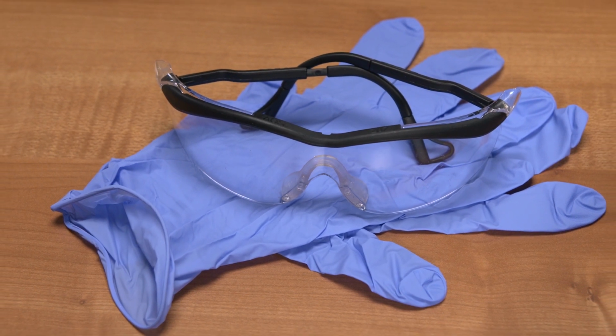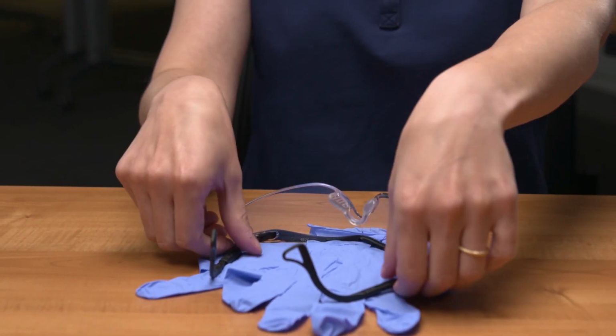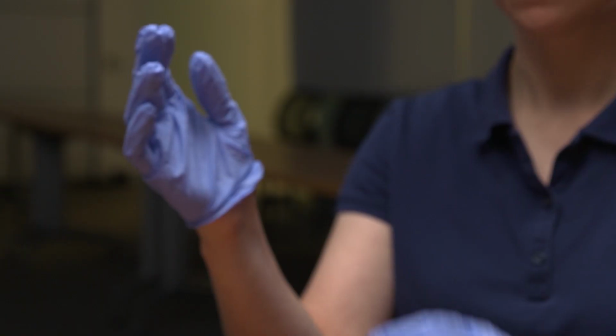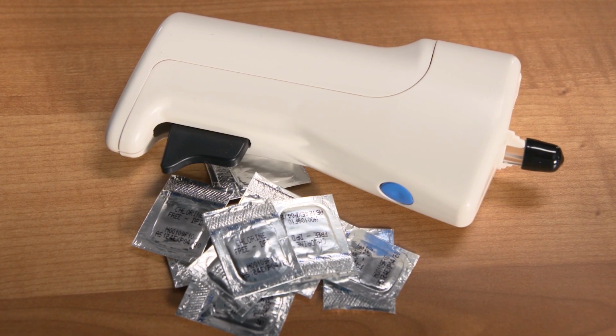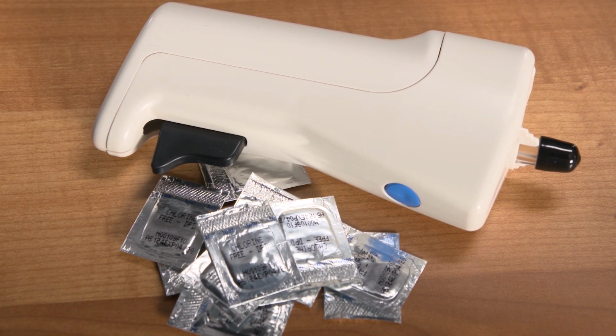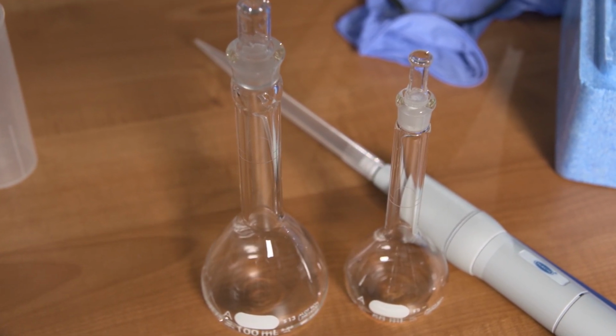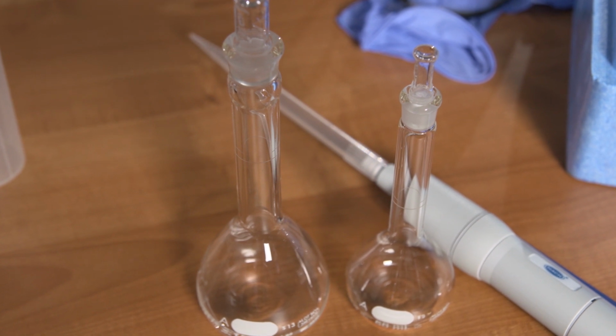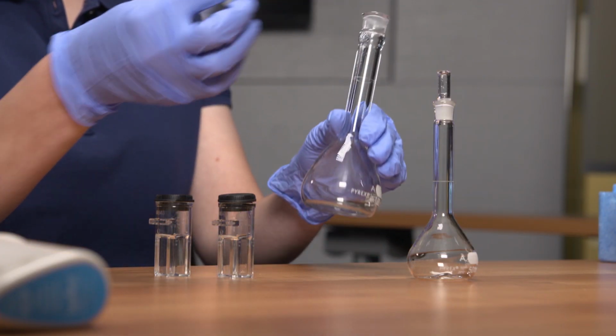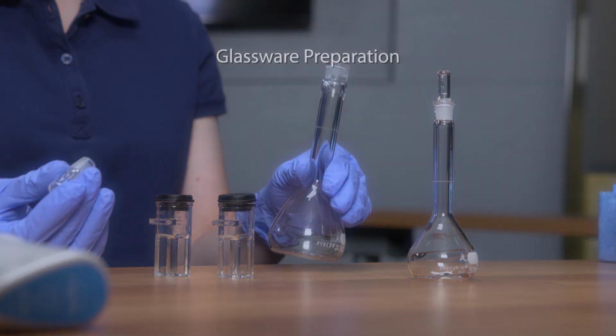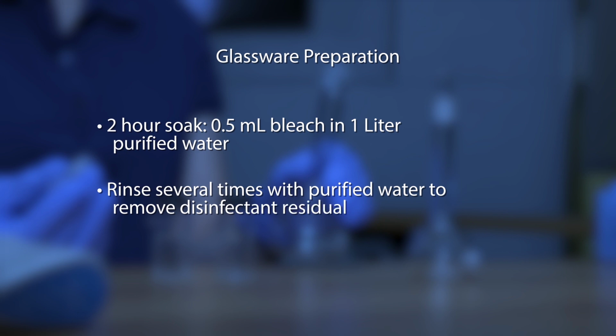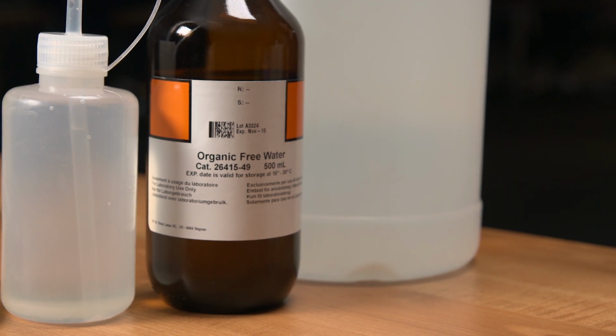We will also want to make sure we use equipment to ensure our safety and keep from contaminating our standards. These include glasses and gloves. We also need to make sure our reagents are prepared properly to prevent contamination of the standards. We want to make sure all the glassware we use does not have a chlorine demand that could alter our standard concentration. We also want to ensure that we do not use the same sample containers for free and total chlorine analysis. Chlorine demand-free glassware can be prepared by soaking the glassware at least 2 hours in a solution of 0.5 milliliters of commercial bleach, added to 1 liter of distilled or purified water, and then rinsing several times with purified water. Purified water, typically either deionized or distilled, is usually acceptable for this procedure.